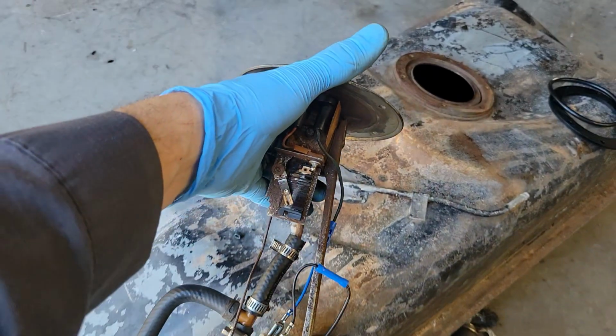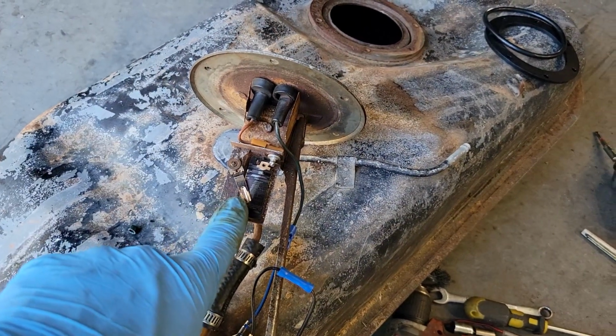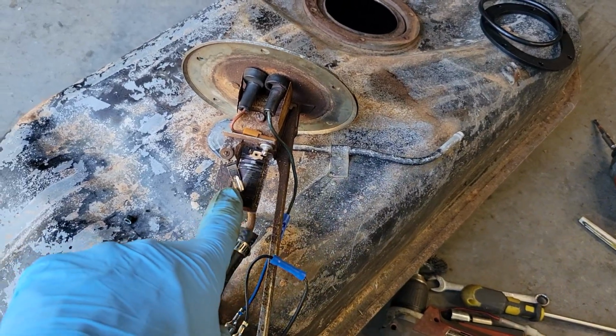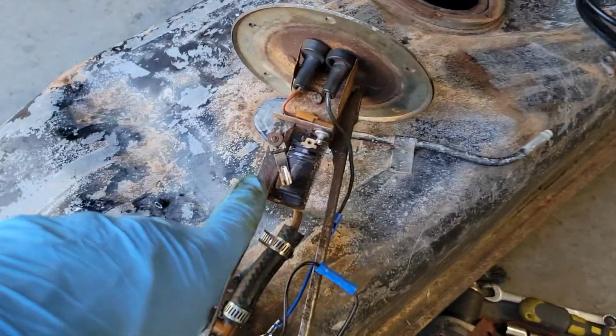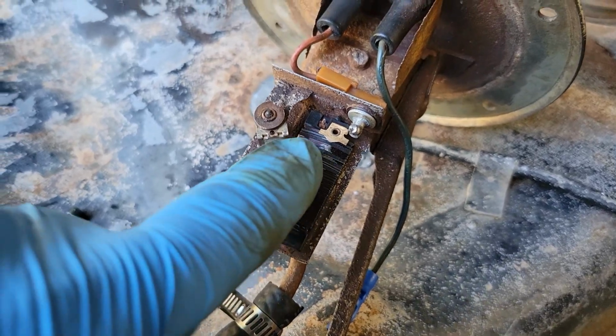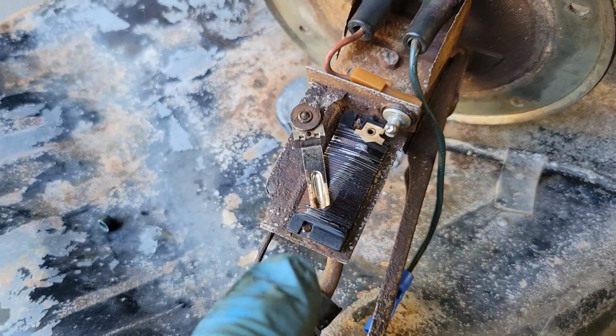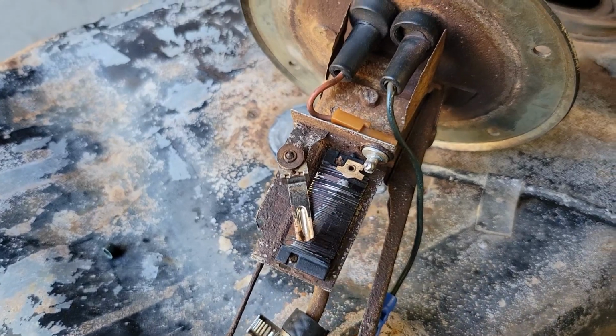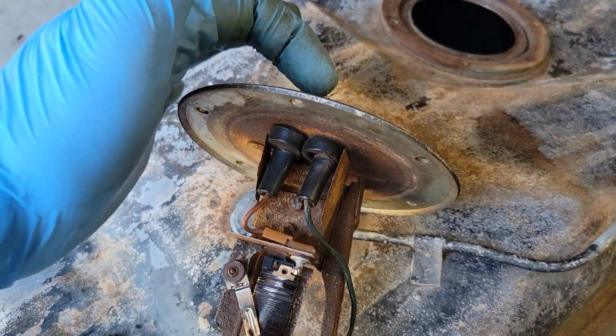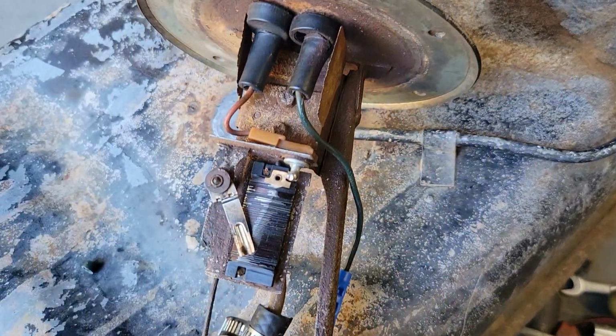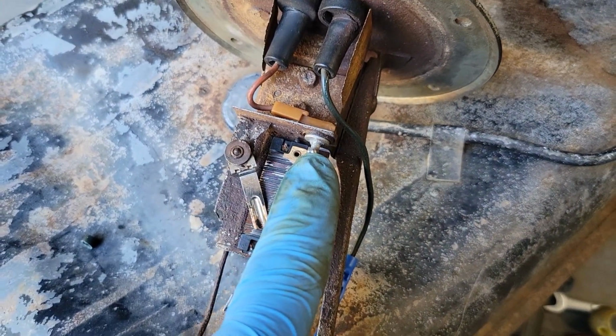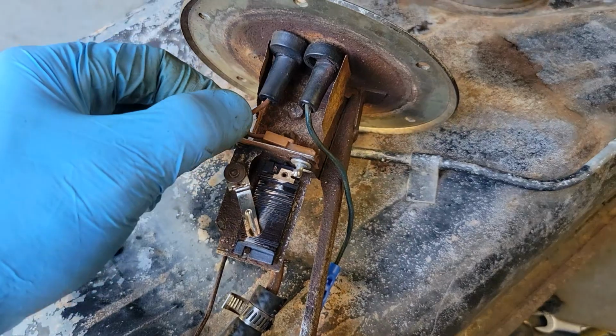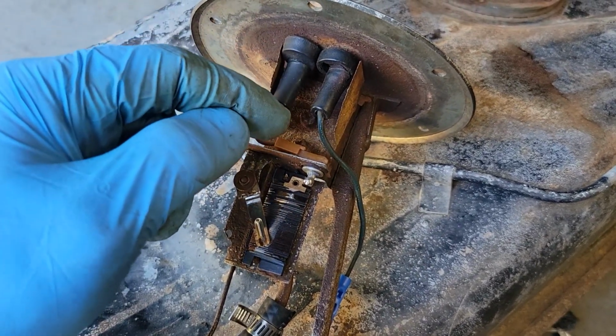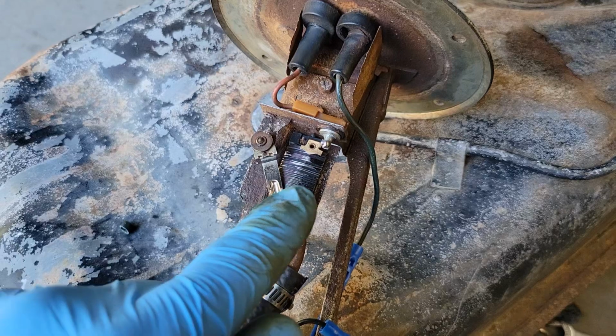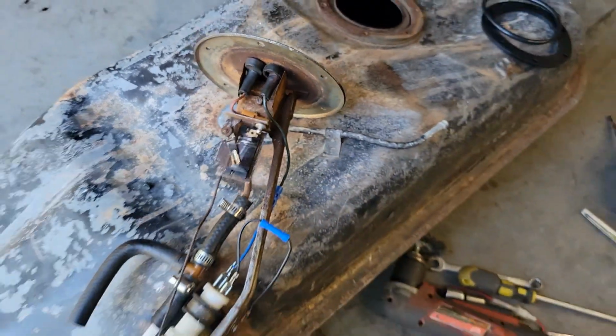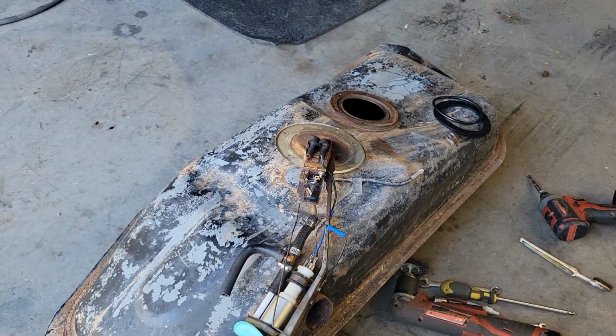To measure the function, you'll put one probe of your meter on this little linkage arm, and then you can put the other probe up here on this brass, and as you move this up and down, you'll see that value change. It's not going to make a difference if you put a probe up here on the spade and then right here on this little stud. Then all you're doing is measuring the static resistance inside the wire. So your gauge is actually reading the resistance in this winding. Anyways, let's stick this thing back together and see if it works.